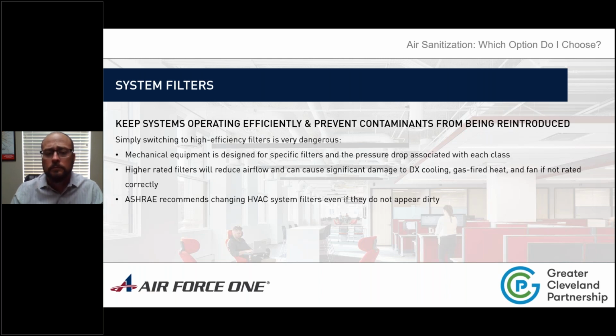Right. And one of the important pieces to this is if you're an organization that has large built-up air handlers that have high static fans that have the ability to be adjusted, they may initially have been designed for a MERV 8 filter, which is very typical design standard. If you're bumping the filters, that type of equipment can be adjusted to maintain airflow, so you can get those benefits. Where we see this as a major issue is on packaged equipment, especially when you start getting into smaller packaged equipment, 3 ton, 5 ton, up to 10 or 15 ton, where the fans aren't designed to go beyond the filters that were originally installed, and you start going to a higher efficiency filter, which does some good.